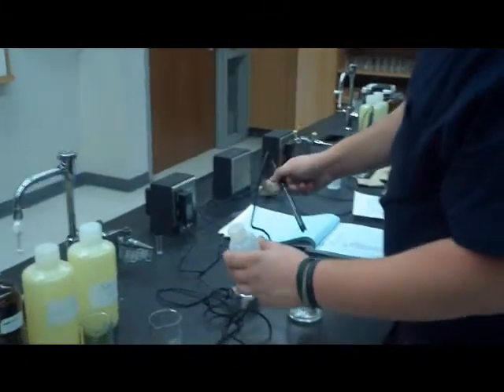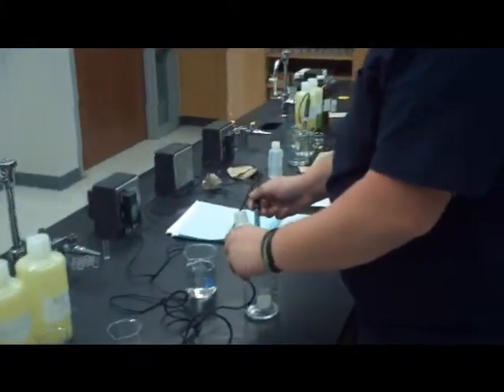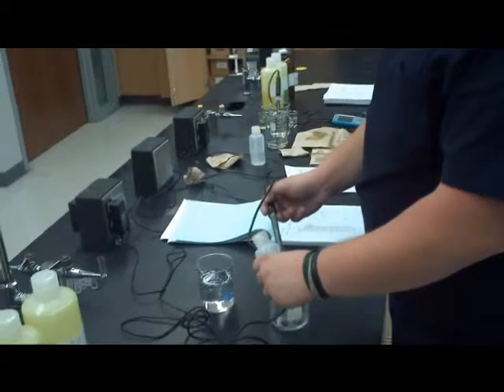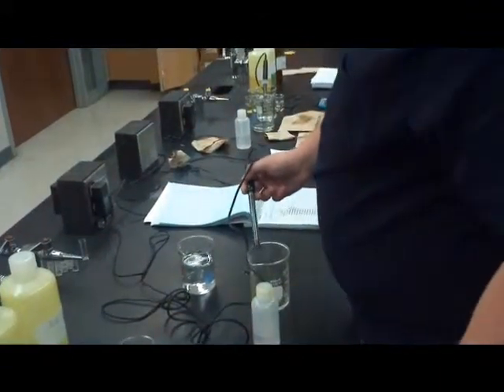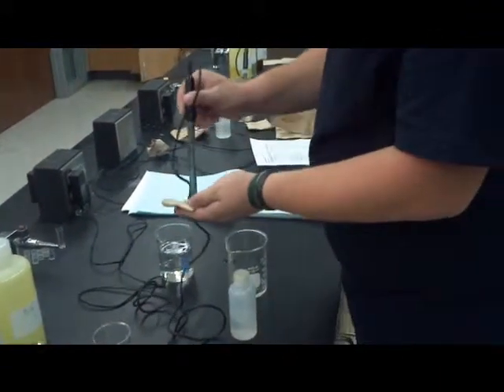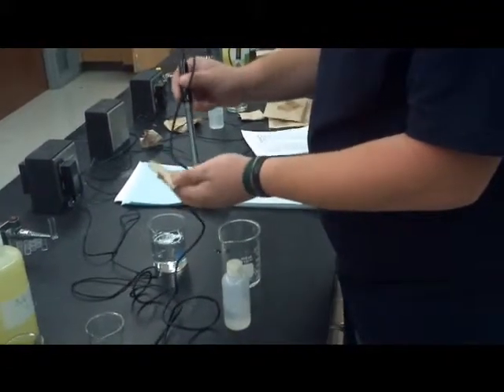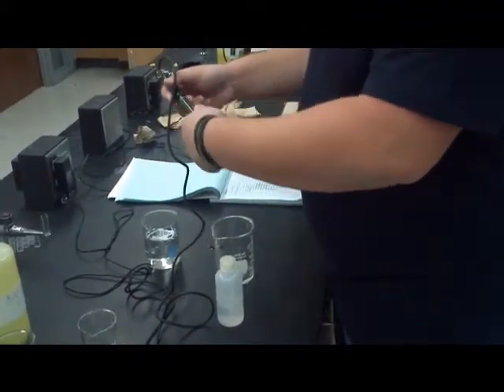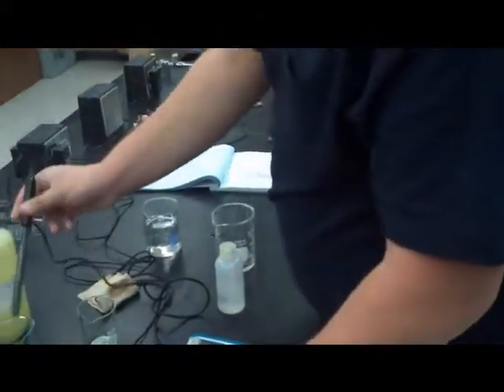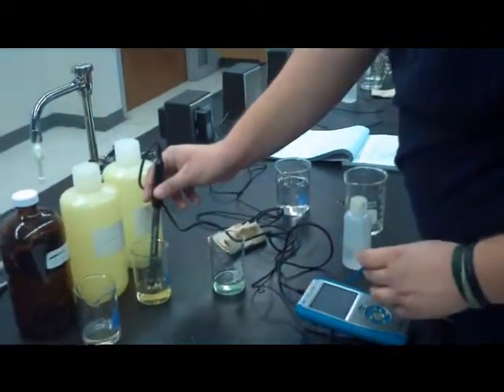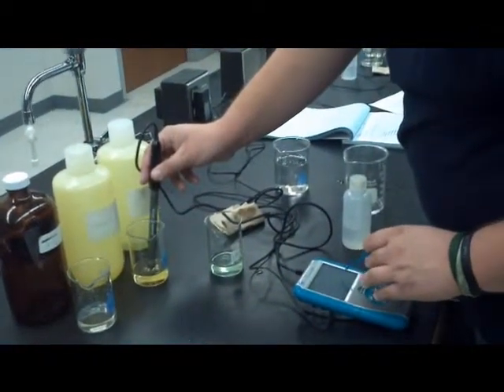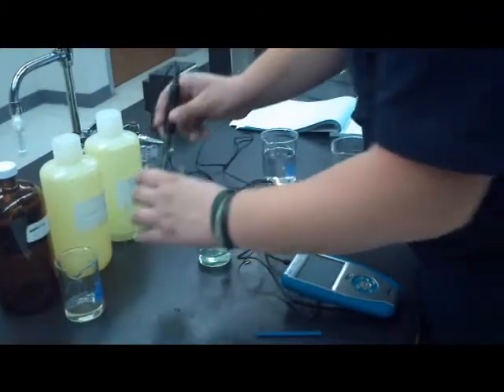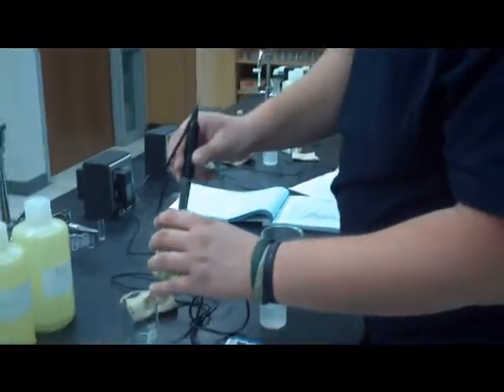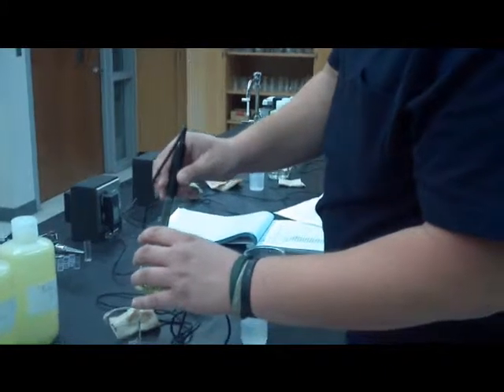The pH probe is removed from the wet solution and rinsed with distilled water. It is dried properly by dabbing. Then the pH probe is placed in the known buffer solution with a pH of 4 because the unknown solution is an acid. Next, the value was typed into the device so it would know what the voltage level meant.